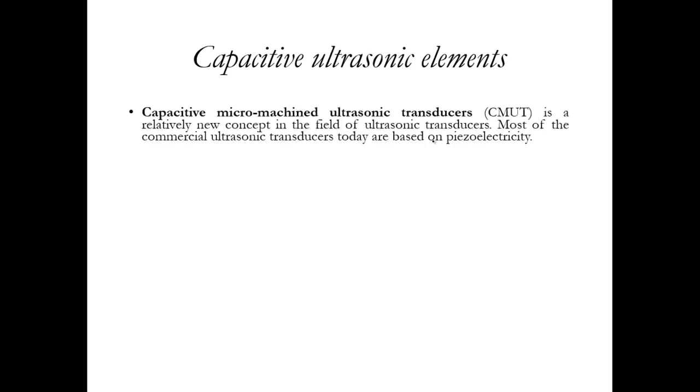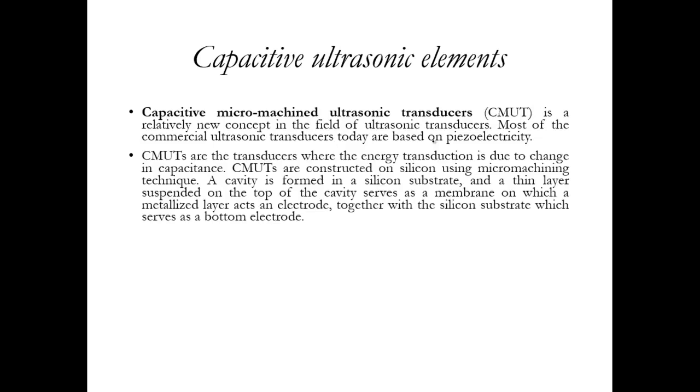Now we have an advanced technology called CMUTs, which is capacitive micromachined ultrasonic transducers. This is just additional information. We can have ultrasonic transducers which are capacitive based rather than piezoelectric based, because we have seen till now that most of the ultrasonic sensors use piezoelectric materials, or piezoelectric crystals. But we may have a very advanced technology called CMUTs, capacitive micromachined ultrasonic transducers. It's a relatively new field, and the energy transduction in this case is due to the capacitance. So they are more MEMS based.